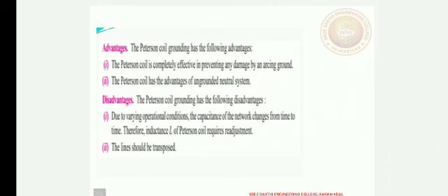Here IF equals IC at resonance. The formula is IF equals VPH by XL and IC equals 3 VPH by XC. By equating the equations, the L value is 1 by 3 omega square C. Next are the advantages. The Peterson coil is completely effective in preventing any damage by an arcing ground. The Peterson coil has the advantages of ungrounded neutral systems. Next are the disadvantages. Due to varying operating conditions, the capacitance of the network changes from time to time. Therefore, the inductance of the Peterson coil requires readjustment. The lines should be transposed.